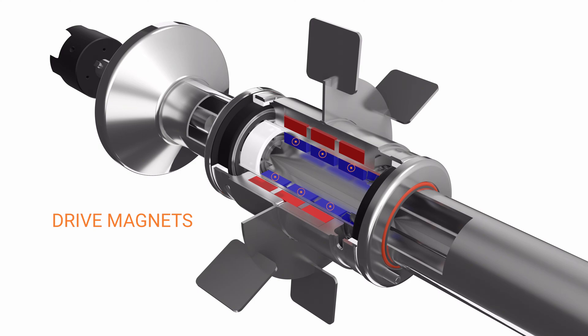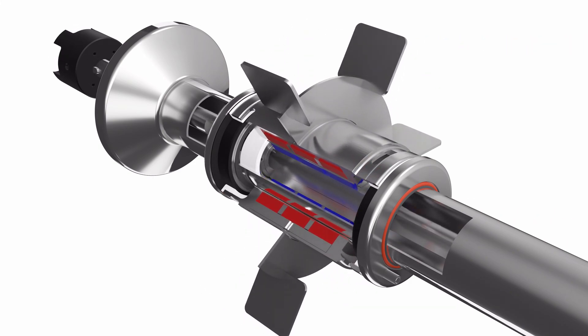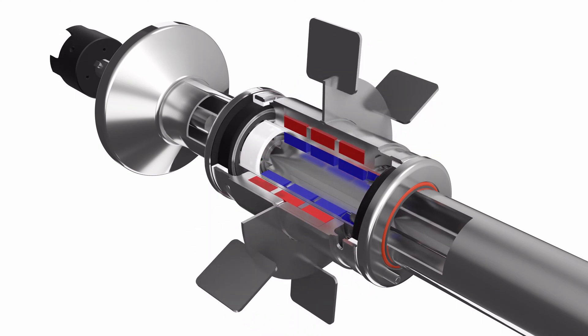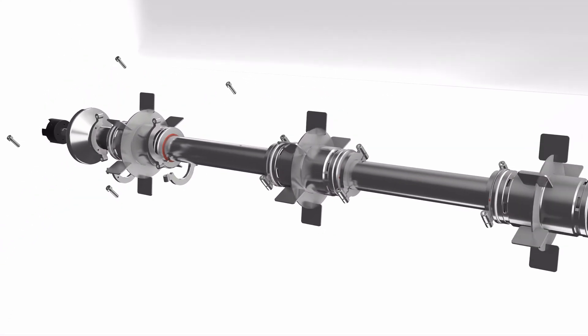Thanks to the magnetic field, they interact with the driven magnets which are placed inside the impeller. As a result, by applying rotation to the drive magnets, the impeller moves simultaneously, thus providing clean and low friction agitation.